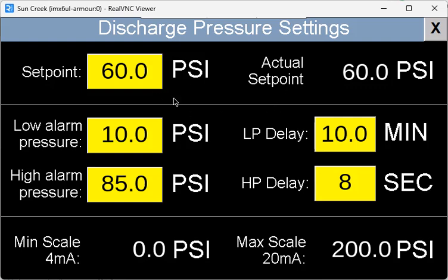So at 60 psi, if you're outputting 100 gallons per minute, if you increase it to 70 psi, you're now only going to output maybe 60, 65 gallons per minute. Similarly, if you were to decrease the pressure, if you only needed 50 pounds of pressure to operate, instead of outputting 100 GPM, you will now put out 105, 110 GPM if you went down to 50 or 55 PSI.